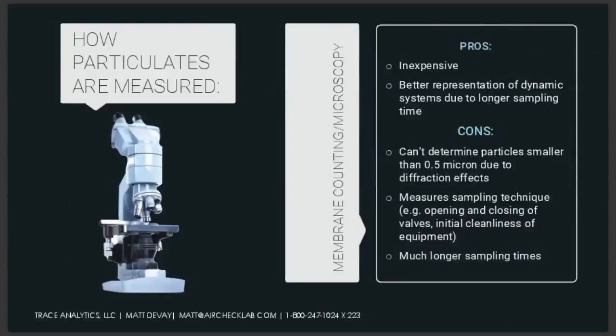Membrane microscopy is another way that people check for particles. This one's a little bit different. You're not getting a real-time measurement anymore. Now you're kind of getting an aggregate measurement, and you're dividing by the volume of gas that's flowing through the membrane. Why would you choose this over other ones? It's not particularly expensive. You get a really good representation of your system over a longer period of time. Remember, these systems are dynamic, and you're kind of capturing more information about the system over an averaged time.